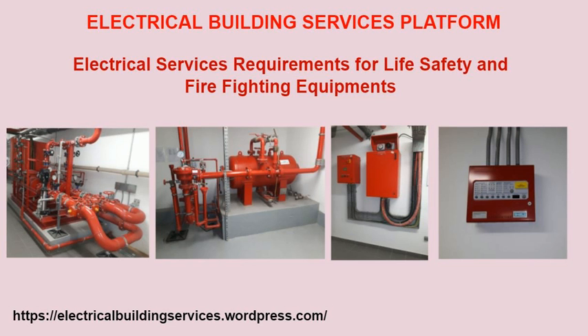Number three, each connection to the power supply should be via an isolating protective device reserved solely for the life safety and fire protection equipment and independent of any other main or sub-main circuit. The isolating protective device to be fed either from the live side or the dead side of the main isolating device. Number four, where a central control room is provided, monitoring facilities should be provided at the central control room to show as far as is reasonably practicable that power is available up to the final control point, e.g., motor contactor, to all fire safety systems.